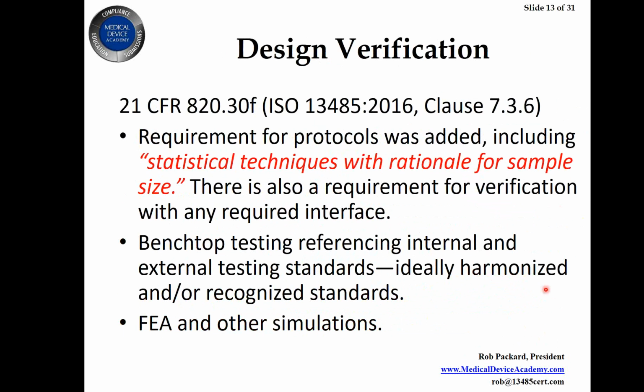For design verification, this is subsection F. As I said before, they've added statistical techniques and a rationale for sample size. So that's throughout this. And a lot of people aren't sure what's verification activities and what's validation activities. They can get confused. And it's not all that hard to get confused when you have something like sterilization validation, which is considered a verification activity. You're verifying that you can meet the sterility assurance claims of the packaging. You're not validating the device in a simulated use.